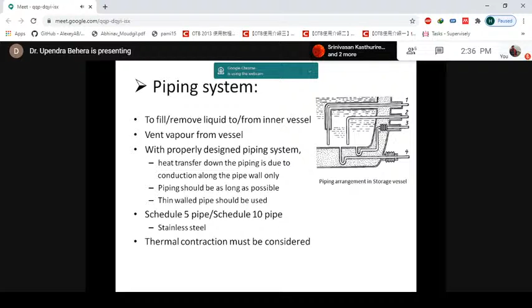There are different configurations we'll discuss next, and generally schedule 5 or schedule 10 pipes are used, as these are thin-walled tubes useful for cryogenic container designs. You also need to account for thermal contraction of the materials used in piping, since material properties change with temperature. All materials have a linear coefficient of expansion, and the same applies for contraction when cooled, though in different regions, so this must be considered, otherwise there will be stresses in the pipeline and a chance of failure.